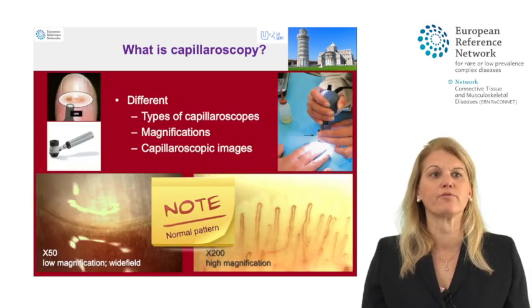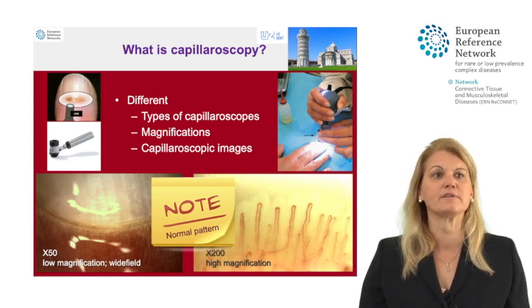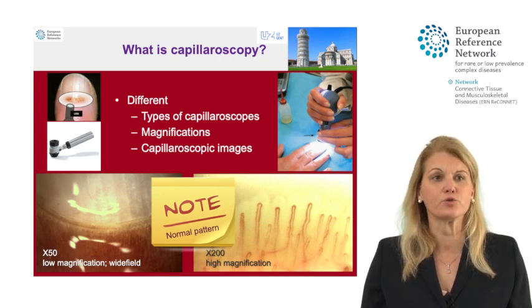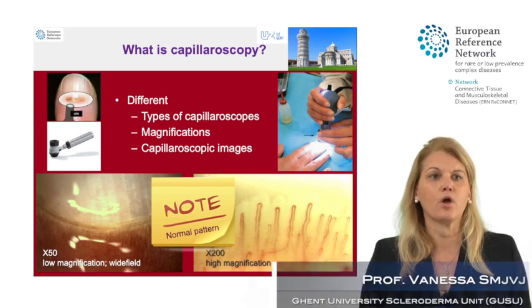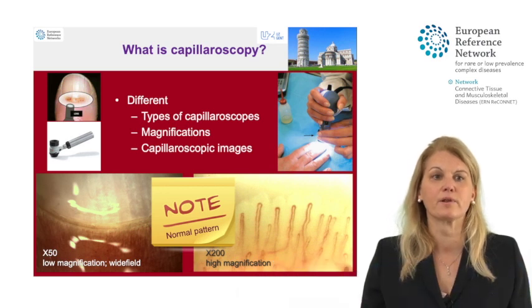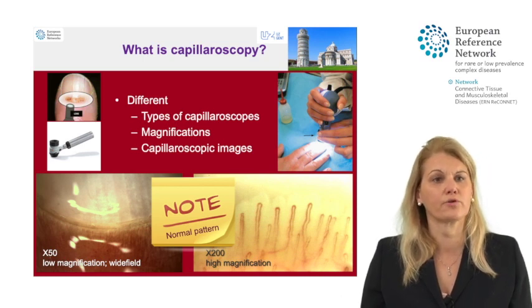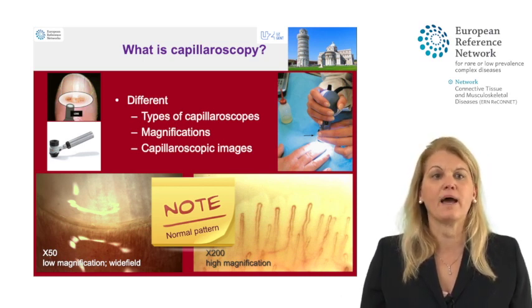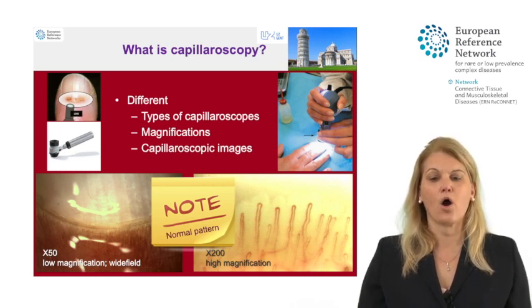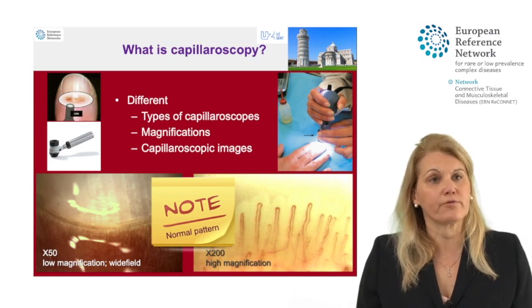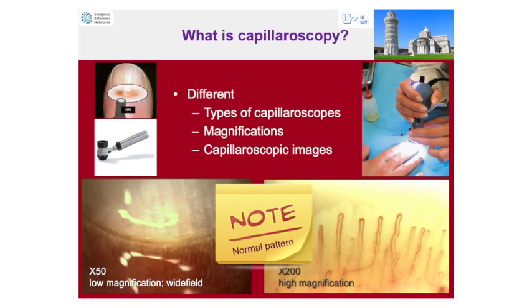Several tools can be used to evaluate the morphology of the microcirculation. On the left-hand side of this slide you can see the dermatoscope, which is still used frequently in the United States. With this tool you have a panoramic view of the nail fold, but you can less well evaluate the morphology of individual capillaries. It is less fitted than the video capillaroscope to identify abnormalities, though dermatoscopes are very cheap and frequently used as first line. On the right-hand side you can see a nail fold video capillaroscope, which allows you to evaluate individual capillaries and discern abnormalities — here showing a normal shaped hairpin capillary.